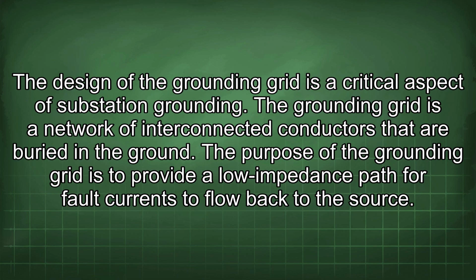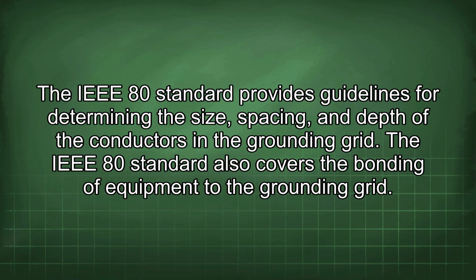The design of the grounding grid is a critical aspect of substation grounding. The grounding grid is a network of interconnected conductors that are buried in the ground. The purpose of the grounding grid is to provide a low impedance path for fault currents to flow back to the source. The IEEE standard provides guidelines for determining the size, spacing, and depth of the conductors in the grounding grid. The IEEE standard also covers the bonding of equipment to the grounding grid.